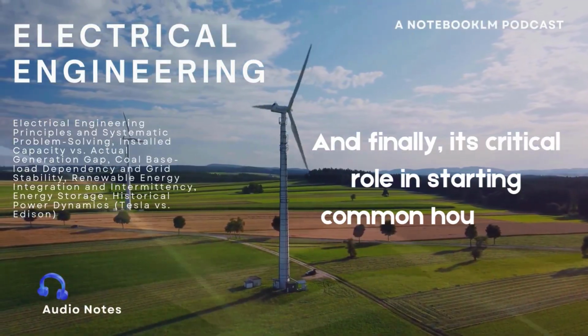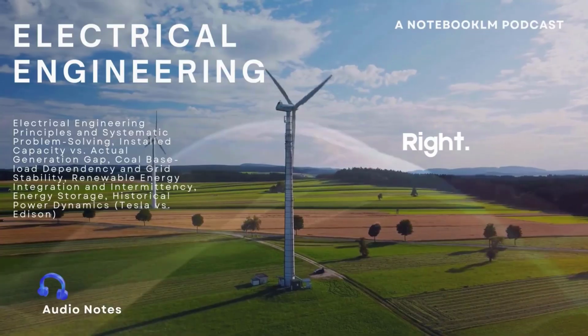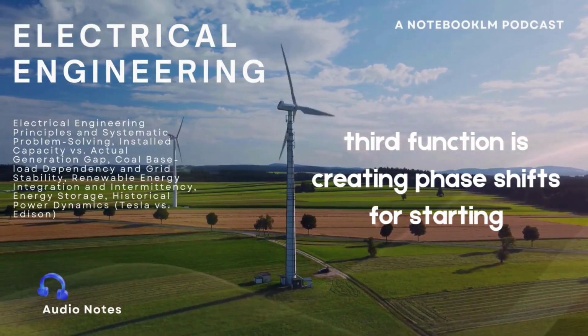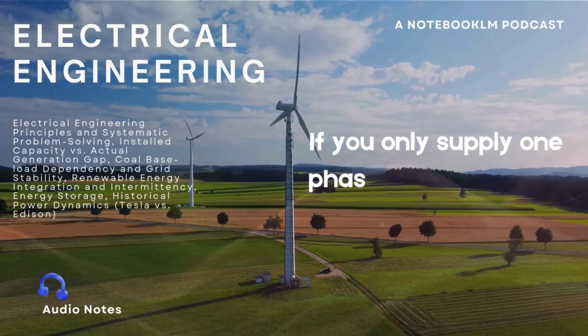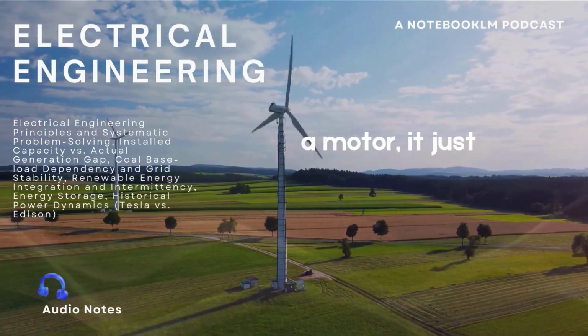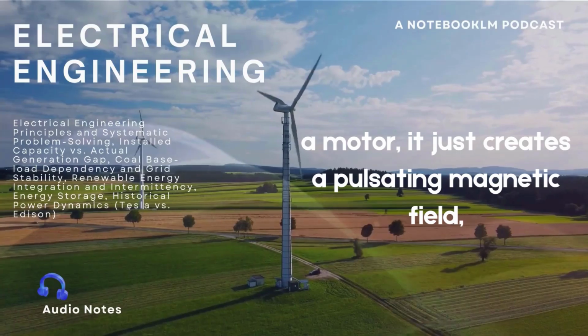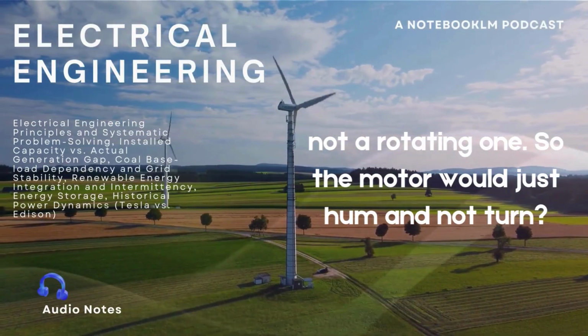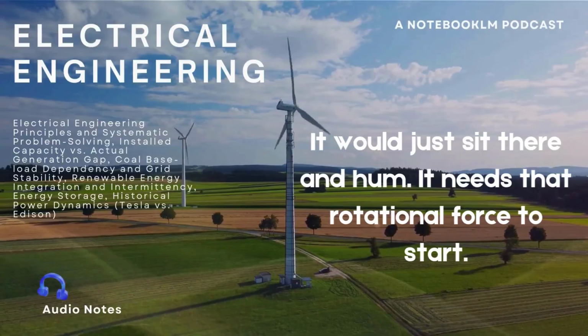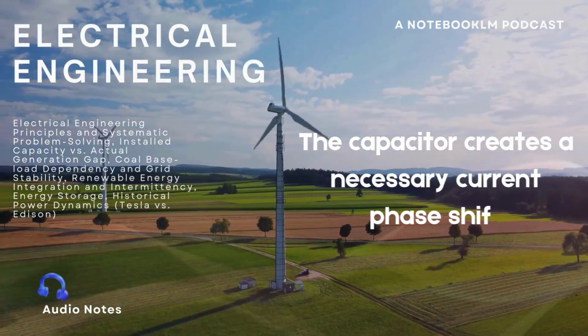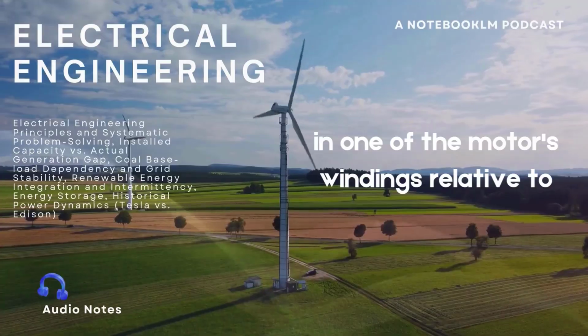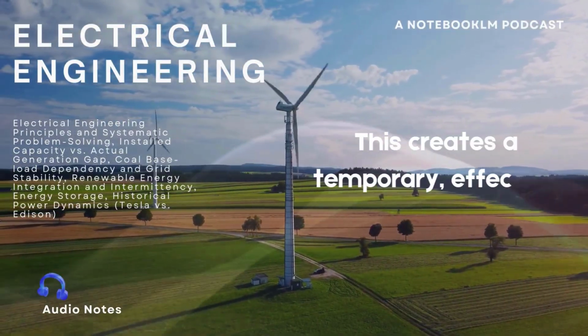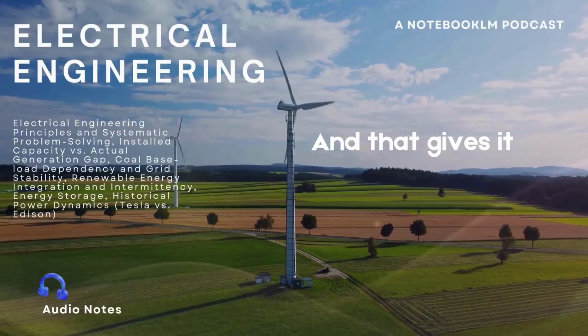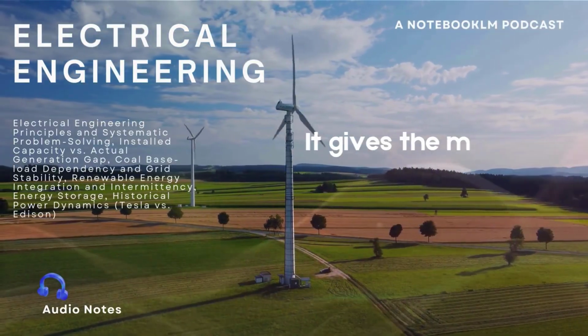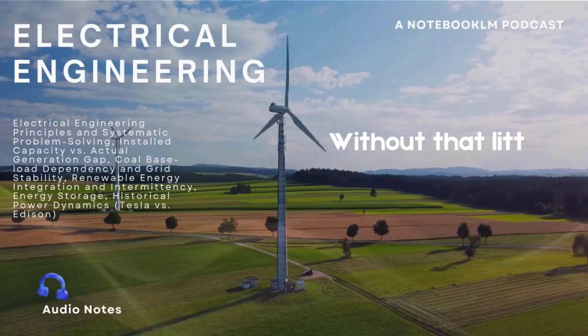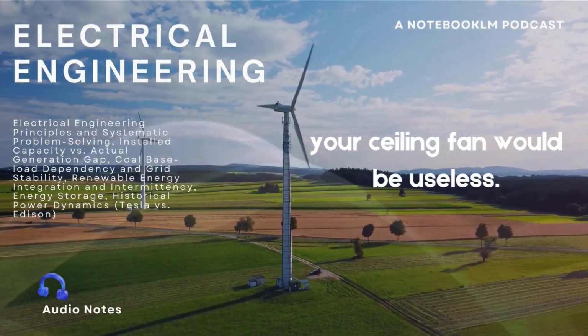And finally, its critical role in starting common household appliances. Right. The third function is creating phase shifts for starting single-phase motors. If you only supply one phase of AC power to a motor, it just creates a pulsating magnetic field, not a rotating one. So the motor would just hum and not turn. It would just sit there and hum. It needs that rotational force to start. The capacitor creates a necessary current phase shift in one of the motor's windings relative to the other. This creates a temporary, effective second phase. And that gives it the kick it needs to start spinning. It gives the motor the starting torque it needs to get going. Without that little capacitor, your ceiling fan would be useless.